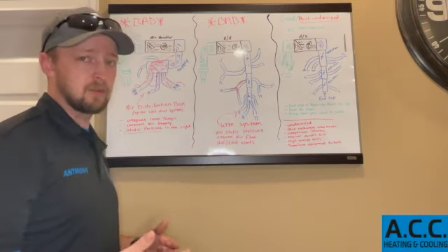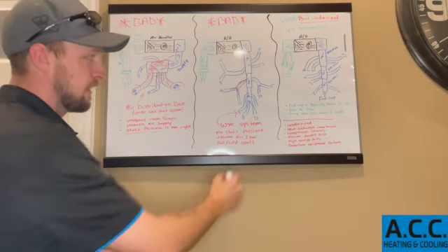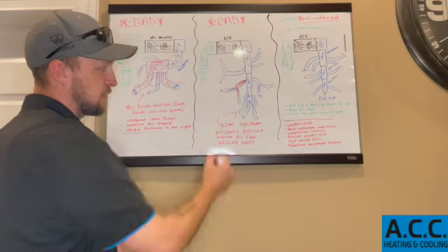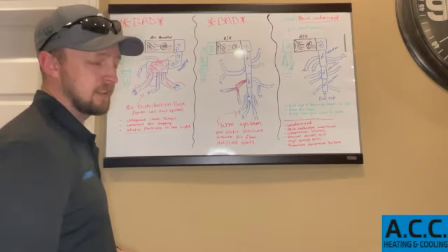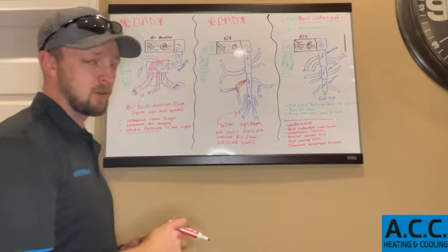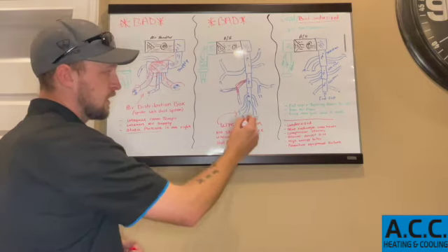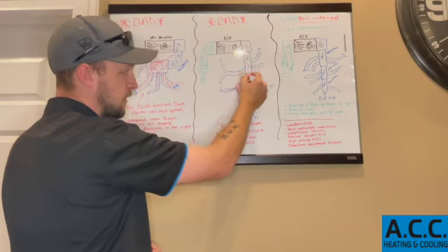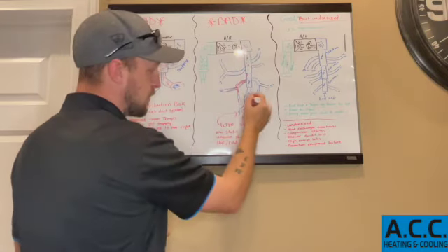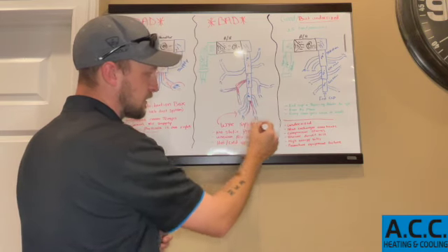And a lot of people are doing that. A lot of companies are doing that. They just run one big flex off of here, split it into 2 smaller flexes, and it really does nothing for your airflow or your hot and cold spots or your static pressure. All this air comes down through here. It's getting smaller so that it's pressurizing in there. But right here at the end, you see it's split off again.